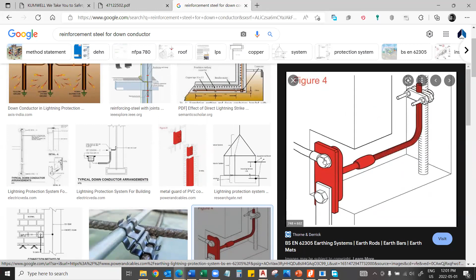And when you are getting this to earth termination, you have links from the down conductor to outwards. So this is when you are using separate conductors for lightning protection, which is mechanically attached to, mechanically and also electrically attached to our own structural elements. So you have to keep in mind that this will be in contact with our structure.